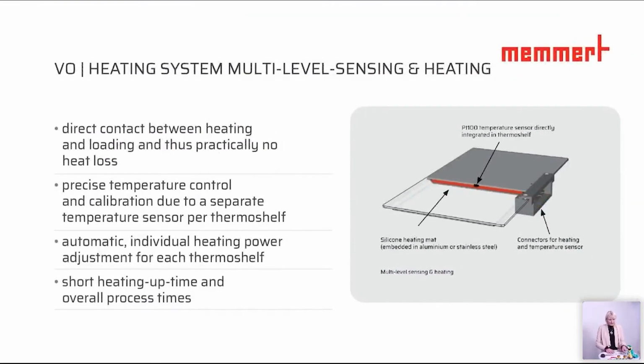Let's go to the next point, which is very interesting and really outstanding about the Memmert vacuum oven: the heating system. I mentioned that when we go for vacuum, we take out the air from the interior. But you have to think, how can there be heat transfer if there is no air in the chamber? That's why we do it differently.